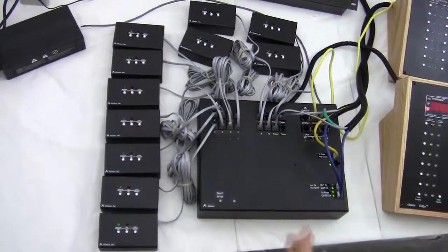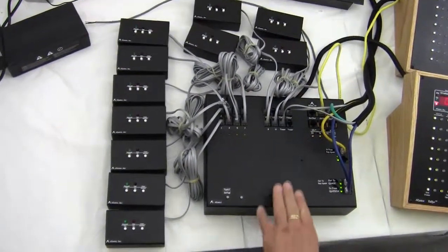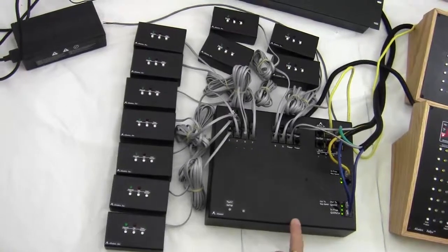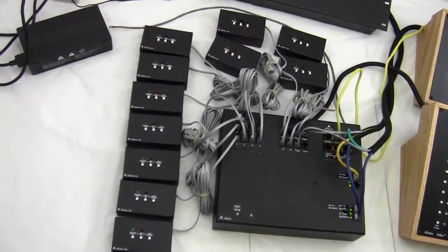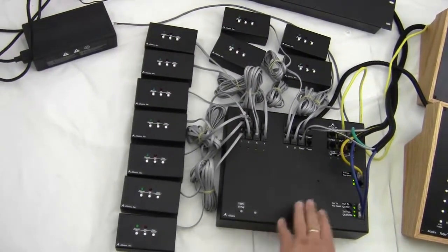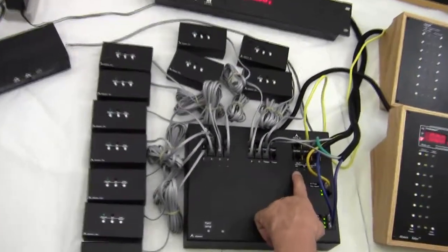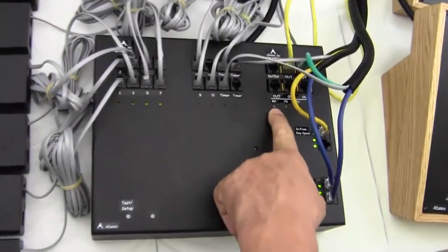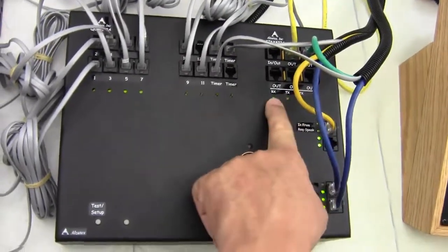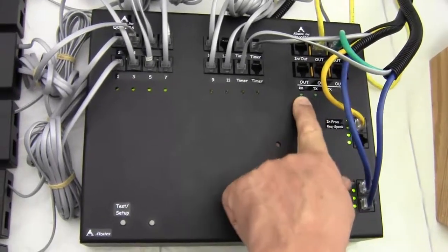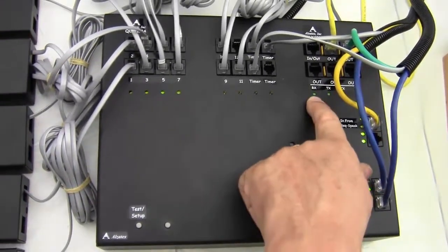Okay, I want to talk about the electronic request-to-speak system with combined electronic voting. And I want to show you a couple little troubleshooting techniques here. First of all, when you first power the unit up, you're going to see these LEDs blinking here. There's 4 LEDs across the top. They should all be blinking. If they aren't, then there's something not correct.